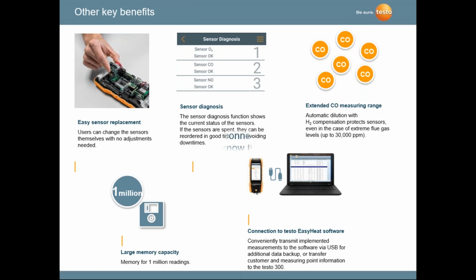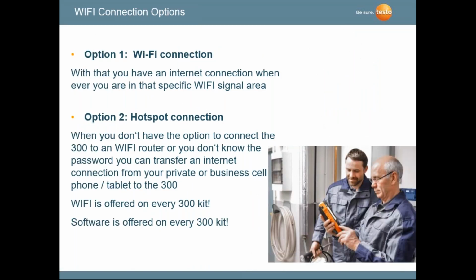Again, memory storage capability. We also added on a 300 Wi-Fi connection. So now you have the capability of taking the readings inside a boiler room and sending them through Wi-Fi, either through a hotspot or a Wi-Fi connection, and send them anywhere you want through the web. So you can instantly take these readings and send them to your supervisor, send them to the customer, whoever you need to show the documentation to. And every 300 has this capability. Every 300 has software that's offered with the analyzer.